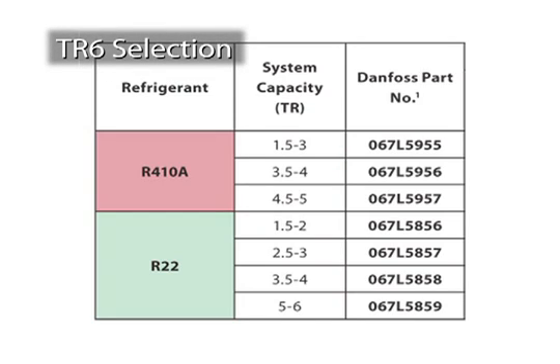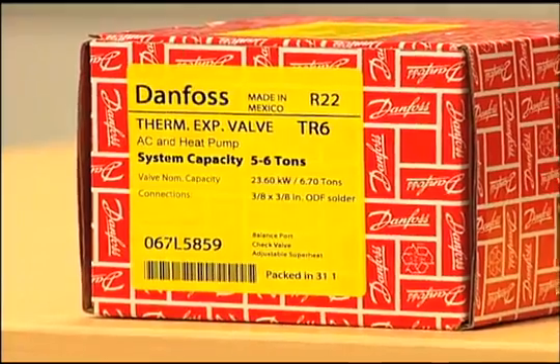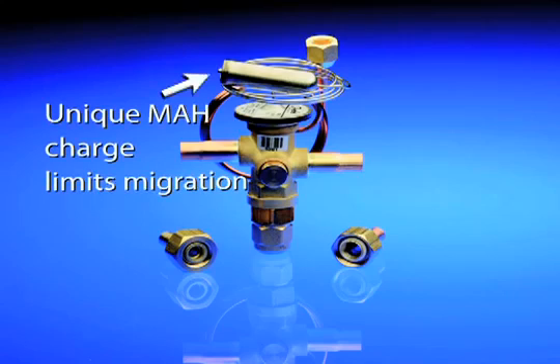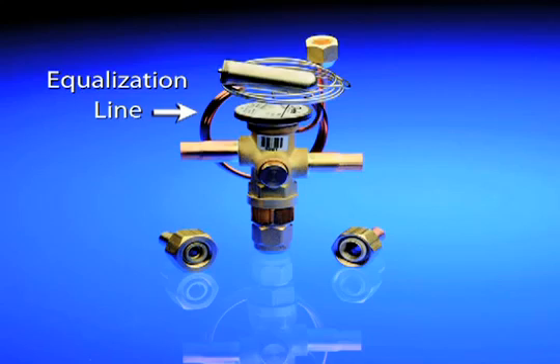Selecting the right TR6 for the job is simple — you only need to know the system's capacity and the refrigerant being used. Each TR6 package clearly identifies the system capacity for which the valve was designed. The TR6 was developed with a unique MAH charge that limits migration and allows for slow opening and quick closing of the valve, meaning the valve is less likely to hunt during changes in evaporator load, permitting the system to establish ideal conditions faster and reducing the chance of flooding the compressor with liquid. The TR6 also includes an equalization line to ensure proper function despite large pressure drops across the evaporator and distributor, which are typical in residential AC systems.